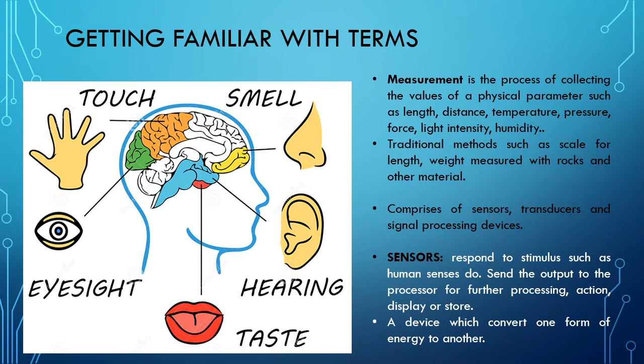The Instrument Society of America defines a sensor or transducer as a device which provides a usable output in response to a specified measurement. The measurement can be a physical quantity, property or condition which is measured, and the output is generally defined by the Instrument Society of America as an electrical output. Basically these are employed to automatically carry out information as well as process monitoring activity.